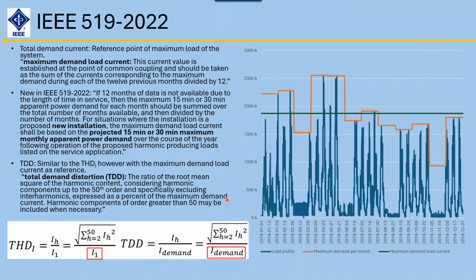Okay. So what the standard has done, and I don't believe they had this in 2014, is they want to look at the maximum load current over a year's period. What I'm showing down here, these brown, that's your actual load. This orange line is the maximum demand for a month. If I actually counted these, I've got 12 of them: 1, 2, 3, 4, 5, 6, 7, 8, 9, 10, 11, 12. Then they take these 12 and come up with a maximum demand. They add all 12 of those monthly maximum demands and divide by 12. And this is the reference point they're going to use for the maximum demand load current.